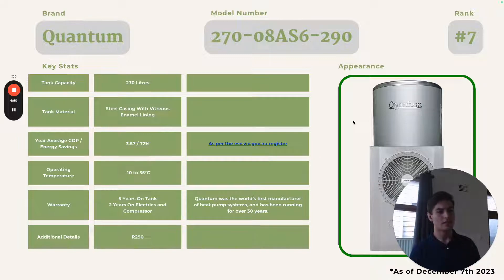All of the systems here interestingly use propane. Propane is a very very good refrigerant to use, not just in terms of efficiency but also in terms of GWP — global warming potential. The one-year GWP of propane is three to four, which means it's actually more than CO2, but if you take it over a 20-year or 100-year time horizon, propane breaks down very very quickly. It's got a 100-year GWP of 0.02, which is significantly lower than CO2.